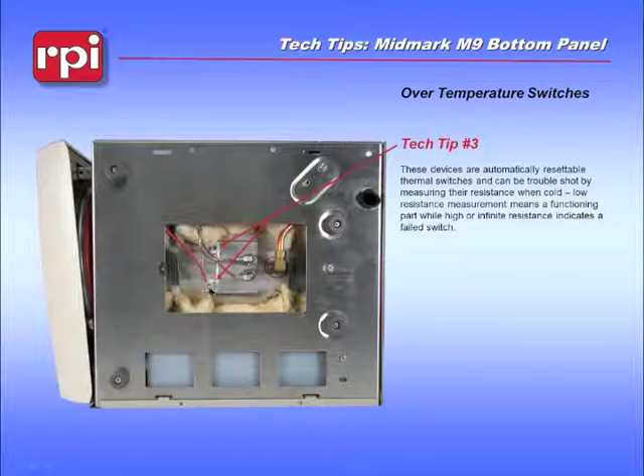One of the problems we have found is that these connections over time can become oxidized. If you actually are working with electricity, you'll know that oxidation creates resistance. Resistance creates temperature, and you actually can build up a small amount of temperature within these connectors, and we want to make sure that they are not artificially triggering these thermal switches early. These thermal switches are very important. The reason they normally trigger is because you've run out of water within the chamber, the steam has superheated, the wall of the chamber has overheated to the point that it releases these devices, and you need to figure out why that has happened and where the water has gone.